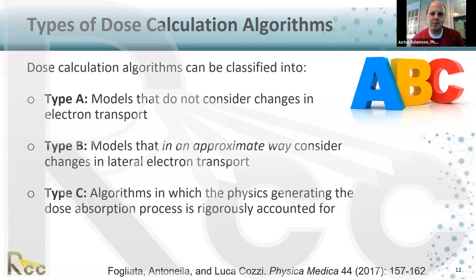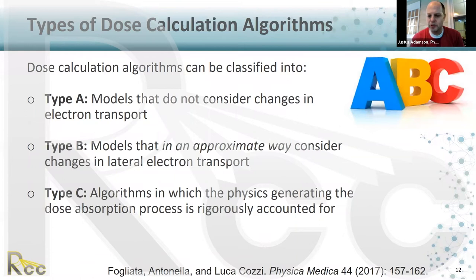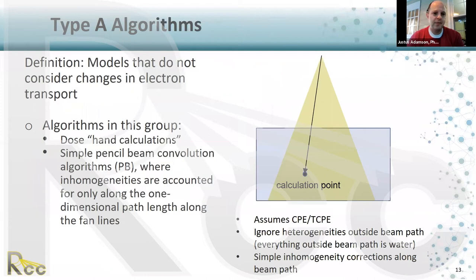Dose calculation algorithms can be classified into three types: A, B, and C. Type A algorithms do not consider changes in electron transport. Type B algorithms consider changes in lateral electron transport in an approximate way. Type C algorithms are those in which the physics generating the dose absorption process is rigorously accounted for.